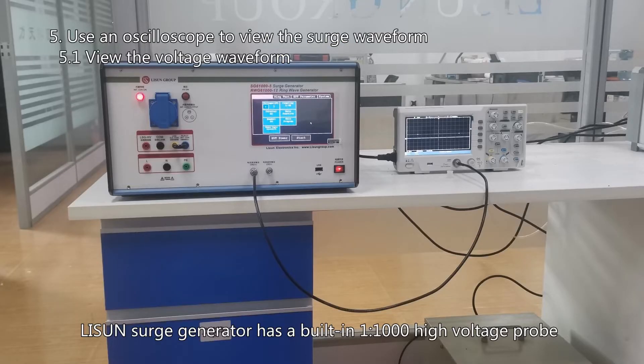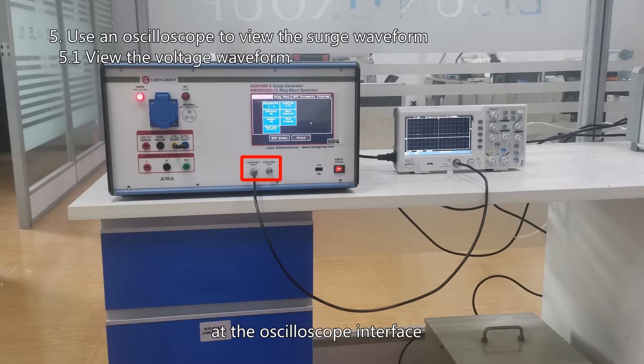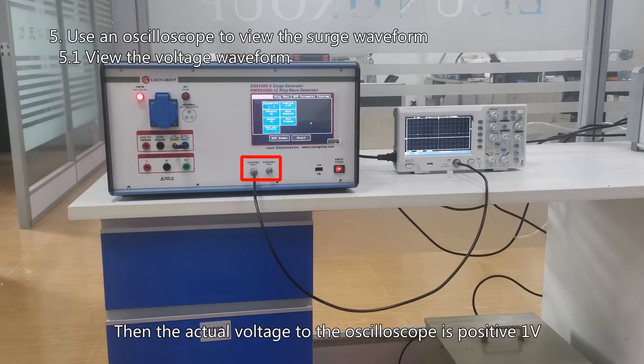The surge generator has a built-in 1 to 1000 high-voltage probe at the oscilloscope interface. Set the surge voltage to positive 1 kV, then the actual voltage to the oscilloscope is positive 1 V.